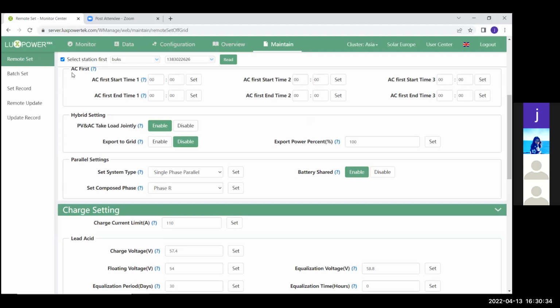Now, AC first. Here's one of the first settings that a lot of people struggle with. If you install your inverter, your AC first settings will always be 2359. Now, if this is 23 and 59, as you see on your screen at this moment, that means your inverter will use Eskom every time, no matter what happens with the panels and the batteries. If there's Eskom, it will use Eskom. And we don't want that at this moment, except if the system is purely a backup system.